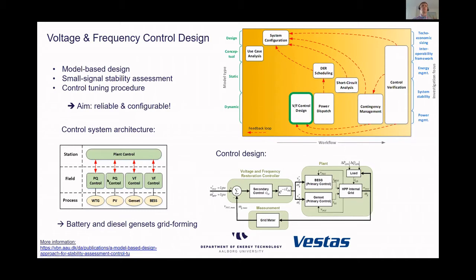Then we can look into various system architectures. The one I came up with uses diesel generators and battery units to so-called form the grid, providing the voltage and frequency reference, while the wind turbine and PV system use standard controls. Then a central plant controller dispatches set points to the individual units. This is just an example of a design architecture.